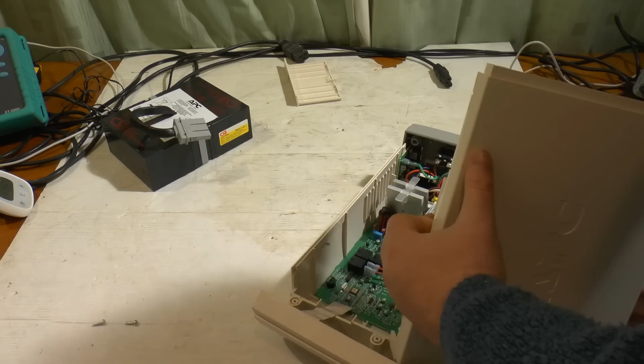Transformer, which is held in by just being sandwiched in between the plastic top and bottom half. These are marked as clamp winding, that's marked as AVR, and that's marked as AVR as well. So this is for voltage regulation, if the voltage is a bit out of whack, into a little bit of tap changing, I believe. So that's on top of the UPS functionality. So you've got the UPS there, and then you've got this AVR transformer here for trimming the voltage.